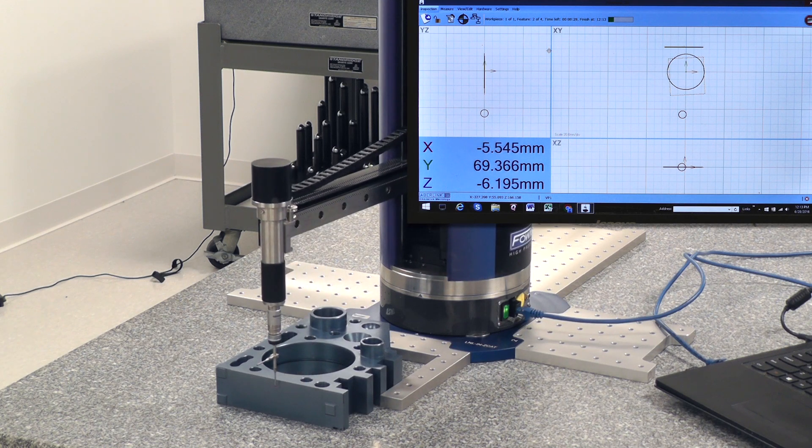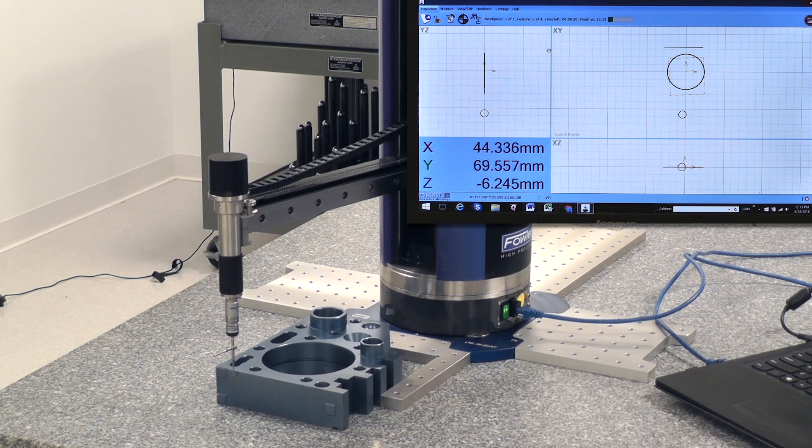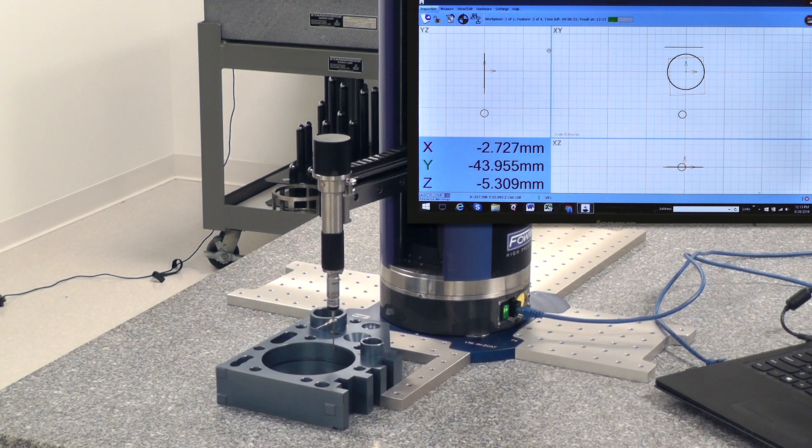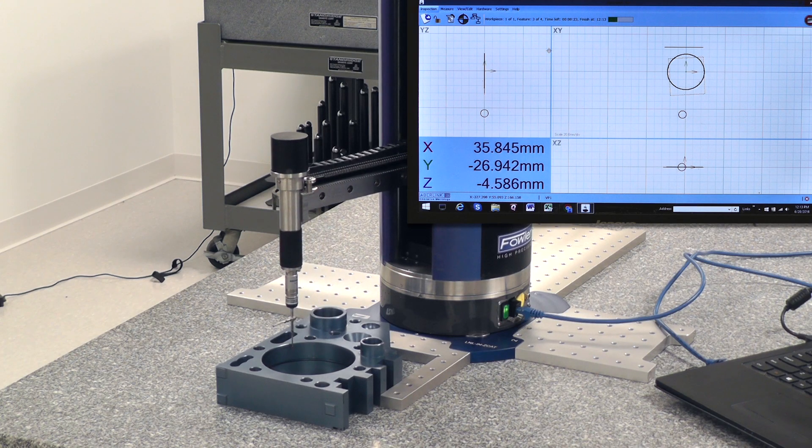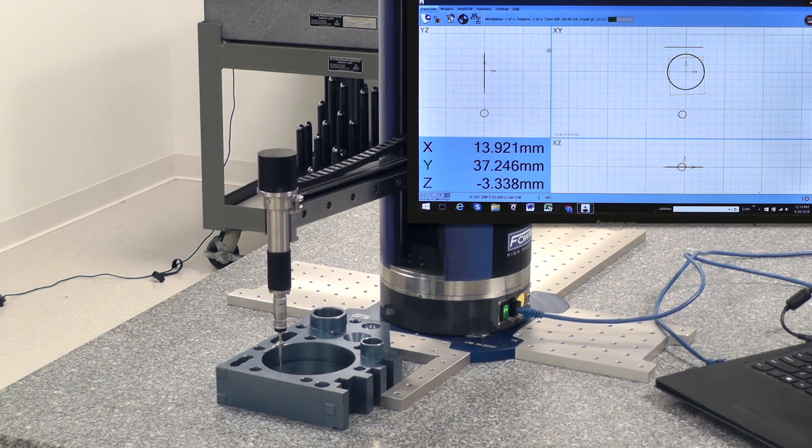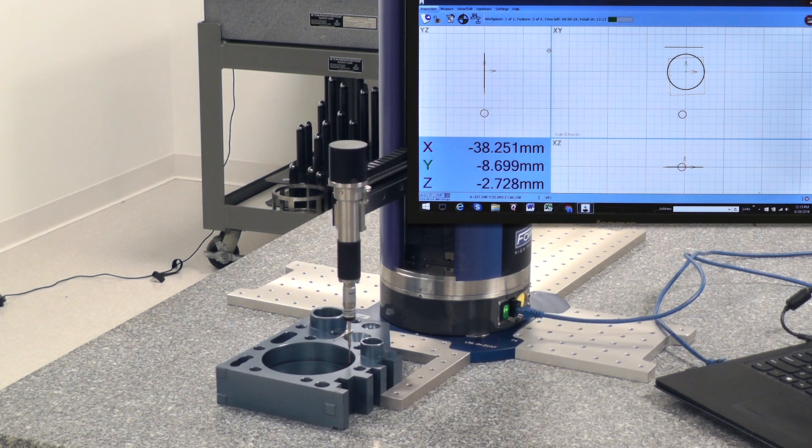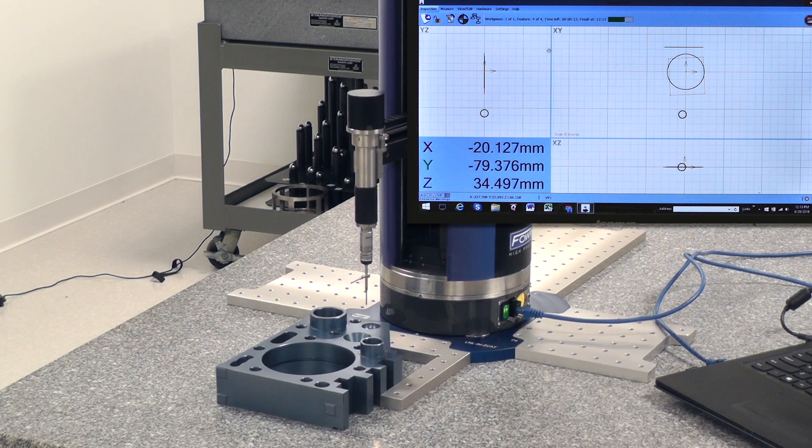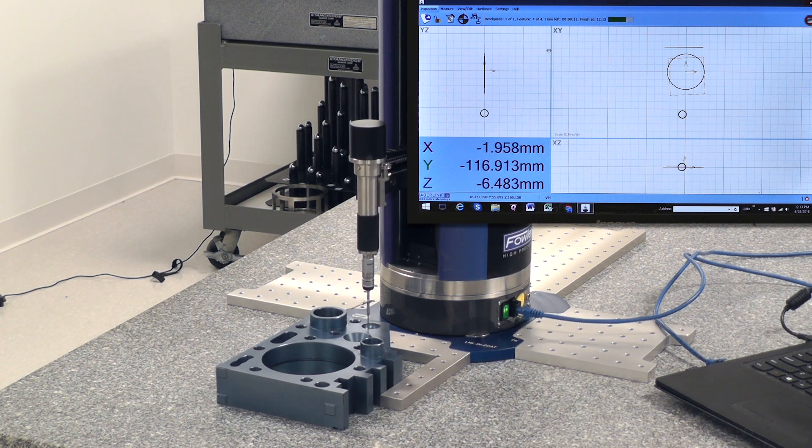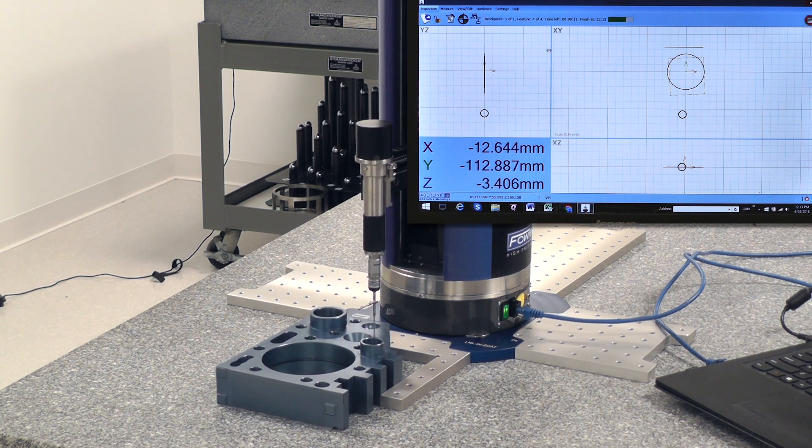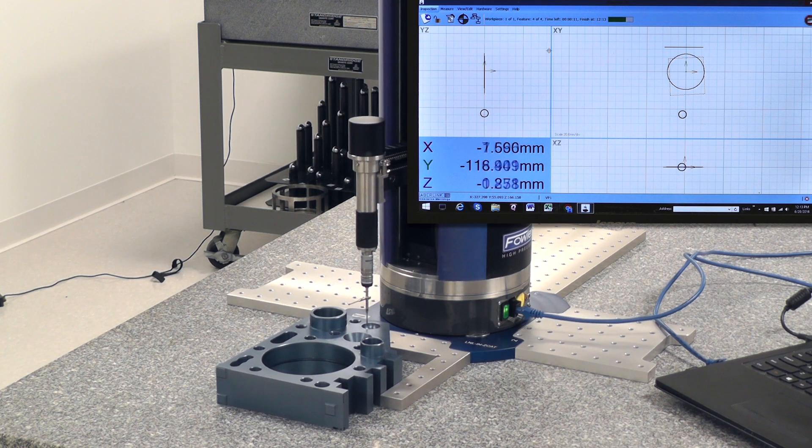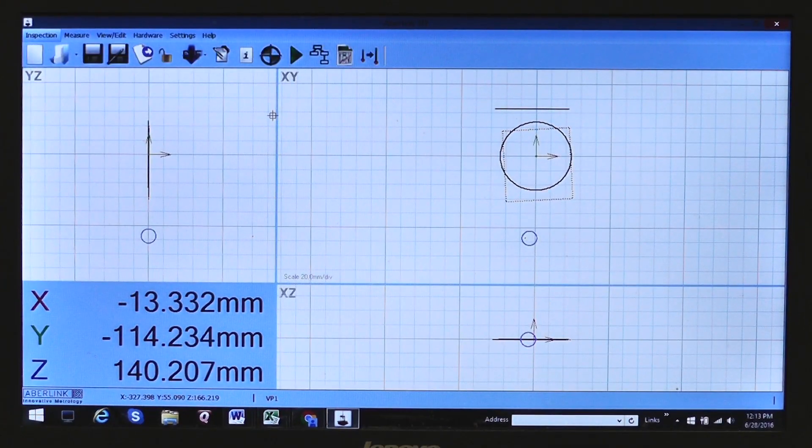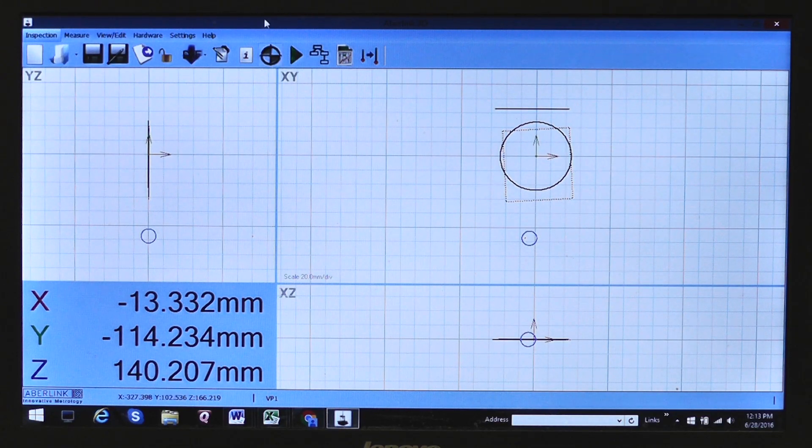We can actually edit every probe hit to be exactly at a certain point that you might want it to be taken, if it's different than what we did manually. So it did the plane, made that plane a reference. It did that line, made that a reference. It's doing the circle now. It's going to make that a reference. And then it should do that sphere. It will go over. Now you'll also notice it's raising itself 20 millimeters above the part. It kind of builds its own safety zone in, so it won't crash into the part. If we needed to account for something that was in the way, we can give it manual go-tos during the teach mode, and it will follow that. So that's the end of that quick program. And you can see how easy it was for me to manually go in there, measure that, and now come back and let it run under DCC.